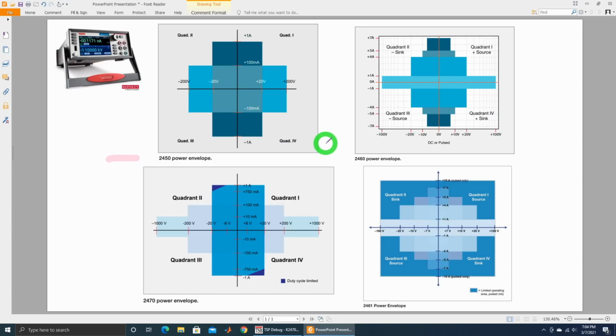The 2460, which I've also reviewed, was introduced for very high power application when you needed a lot of current, so it goes up to 7 amps. It still maintains plus or minus 100 volts. Remember, all these instruments are always 4 quadrants, of course. Those are true source measure units. The 2461 is a unique instrument because not only does it have the same power profile as the 2460, but it has a dual 1 megasample per second 18-bit digitizer built into it, giving it a lot of new capabilities, including pulse support, and I've also reviewed that too.